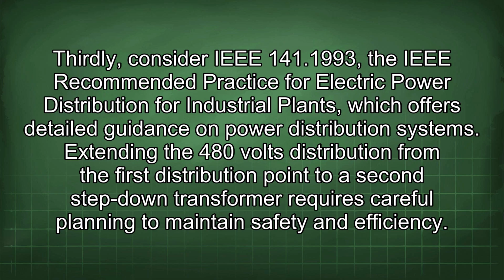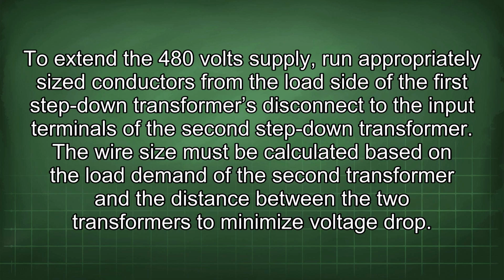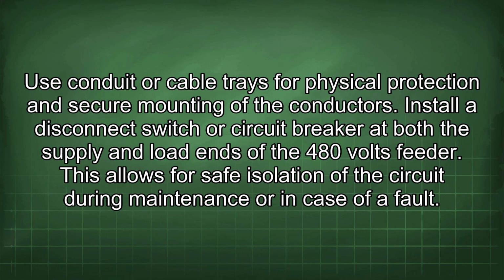Extending the 480 volts distribution from the first distribution point to a second step-down transformer requires careful planning to maintain safety and efficiency. To extend the 480 volts supply, run appropriately sized conductors from the load side of the first step-down transformer's disconnect to the input terminals of the second step-down transformer. The wire size must be calculated based on the load demand of the second transformer and the distance between the two transformers to minimize voltage drop.